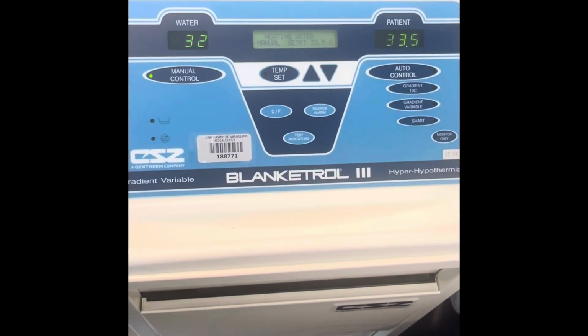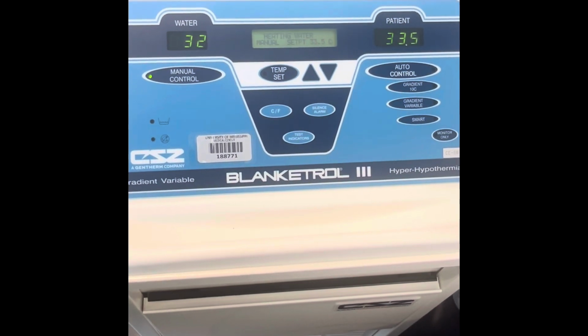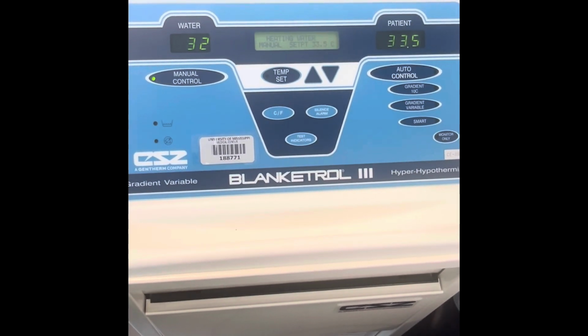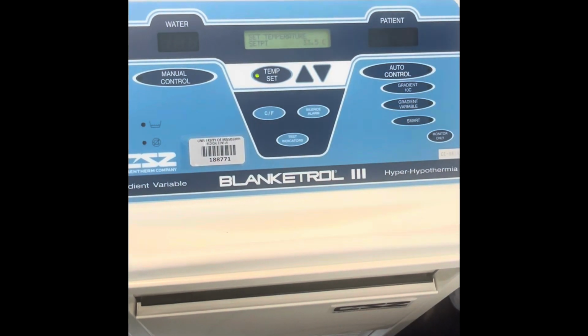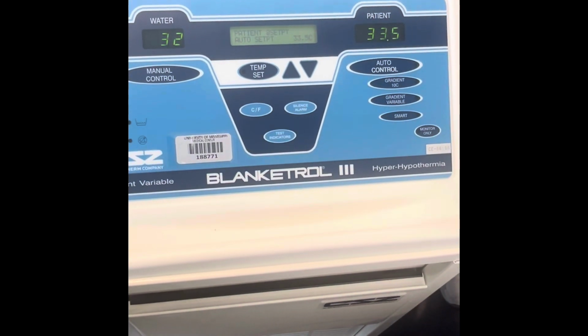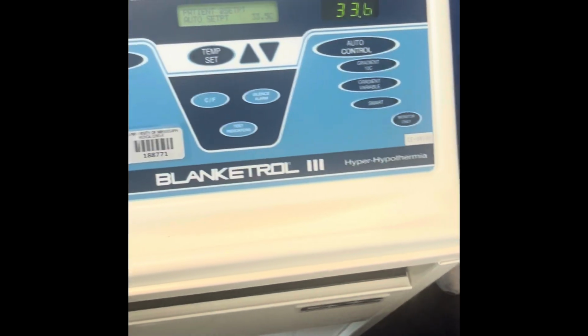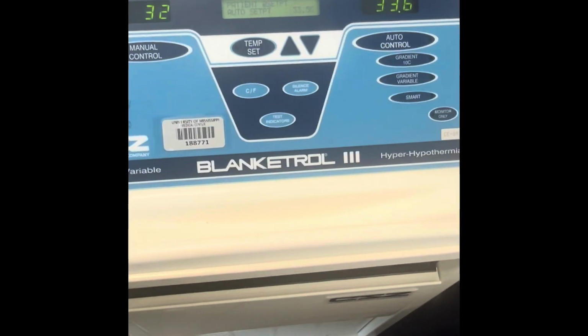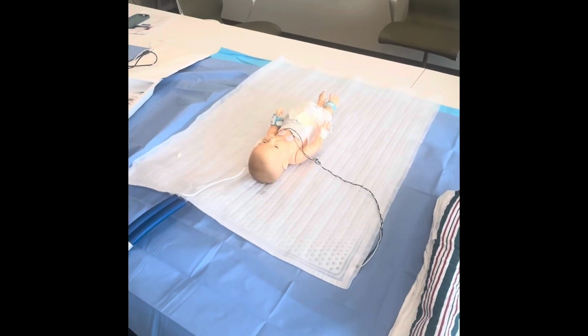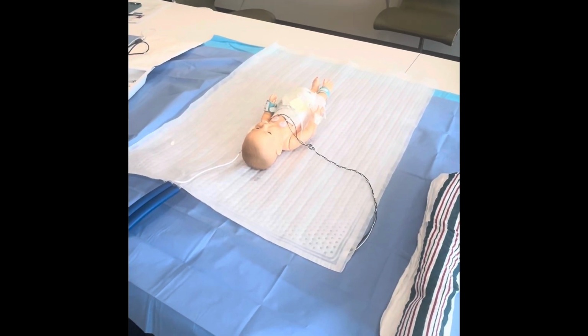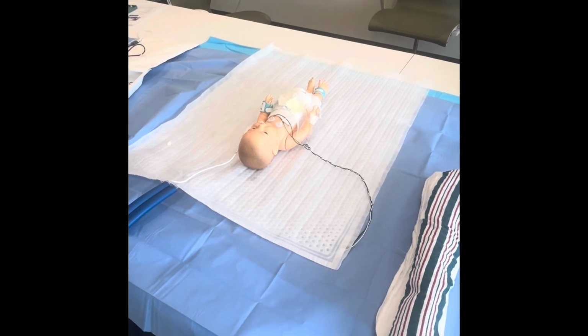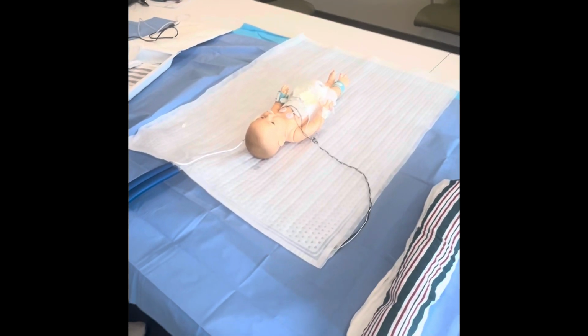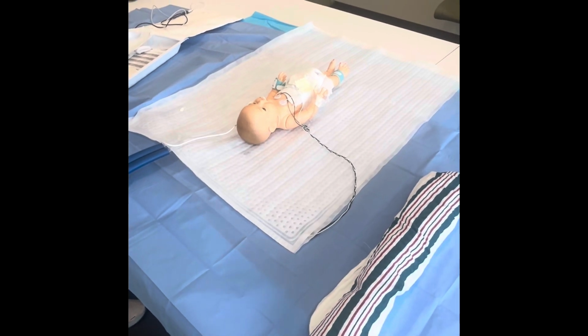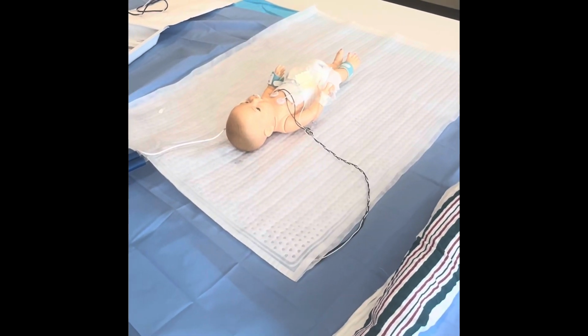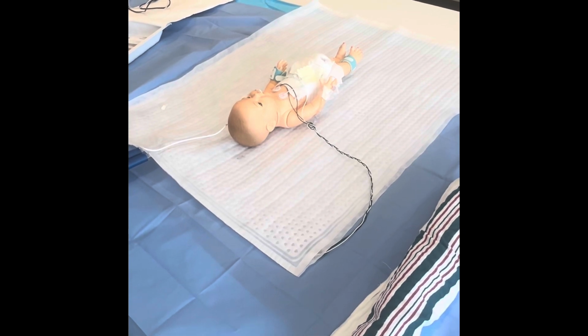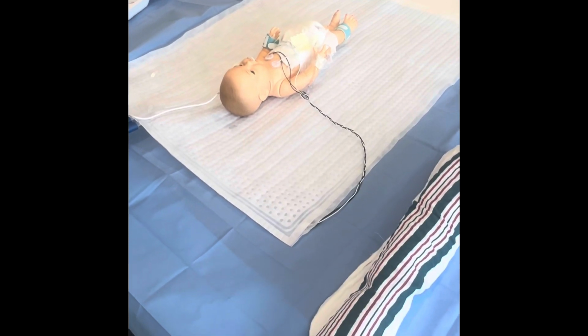You will switch the machine from manual mode to auto mode by hitting the temp set button, then the auto control button. Then you will see the patient's temperature register on the machine. Once you are in auto mode, the patient will remain on the cooling blanket for 72 hours. While you are on the blanket, the nurse will monitor vital signs, urine output, and do thorough skin assessments.